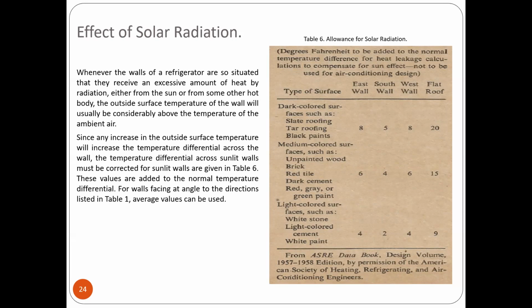So allowance for solar radiation. So degrees to be added to normal temperature difference for heat leakage calculation to compensate for sun effect. Not to be used for air conditioning design. Yan. Ito yung mga type of surface. So i-add mo ito kung na east, south, west. I-add mo yan. Flat roof, 20. Okay, these values are added to the normal temperature differential. For walls facing at an angle to the direction listed in table 1, average value can be used.